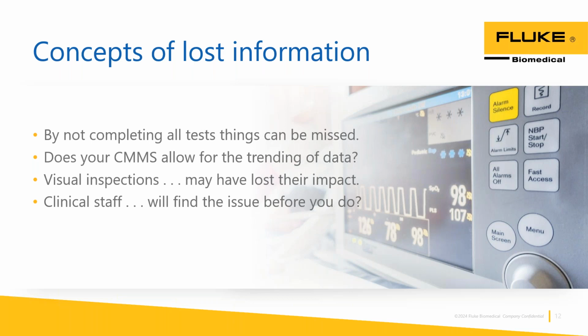Could it be a low important step? Maybe. Could it be a high important step? Maybe. But are we getting each and every one of those tests performed and making sure they're done? Does your CMMS allow you to capture that actual data and do anything with it? Can you do some trending with the data? Maybe you can start to look at the data if you're able to capture the actual results, and see when all of a sudden your readings are starting to go up, or maybe starting to go down.